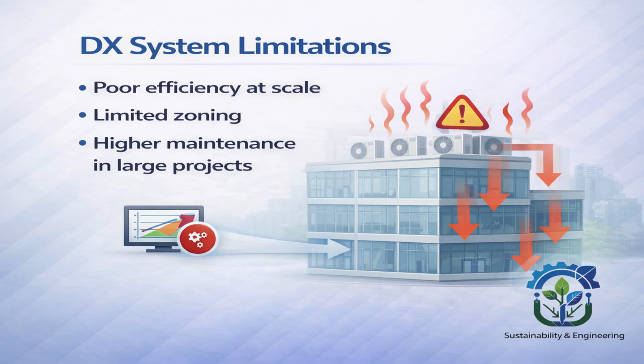A DX system works efficiently when the project is small, but as the building size increases, we end up installing many individual outdoor units. Each unit runs independently with no load sharing and no optimization between zones. So instead of one optimized system, we get many small compressors running inefficiently, especially in hot climates in regions like the Middle East, UAE.